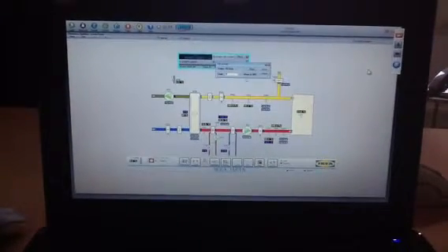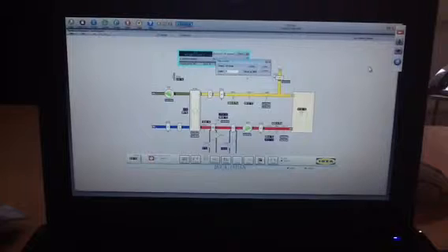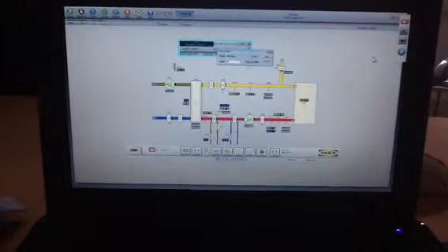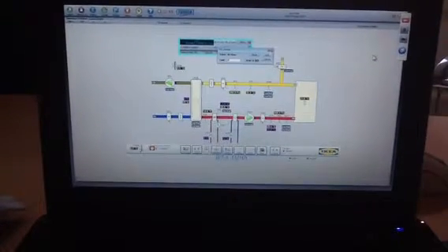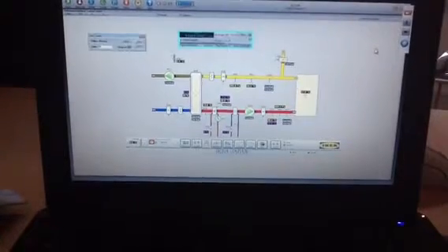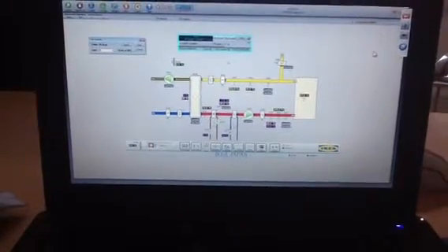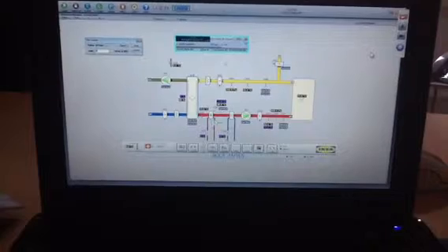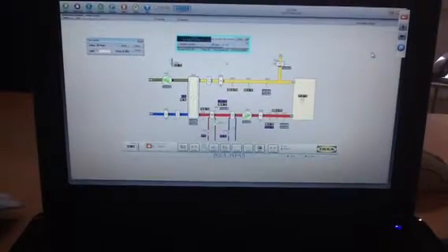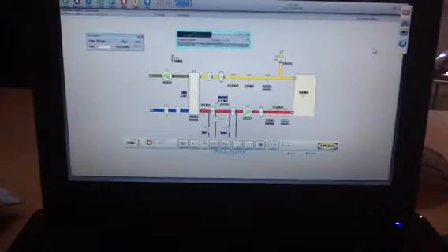The next one is the trip counter, where you can see the running period for that object. You can also set an alarm for a long run time, or if you would like to change the wheel belts or anything else needed, you can have an alarm at 90%.